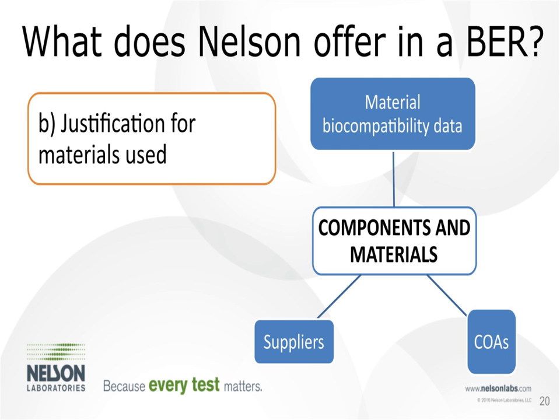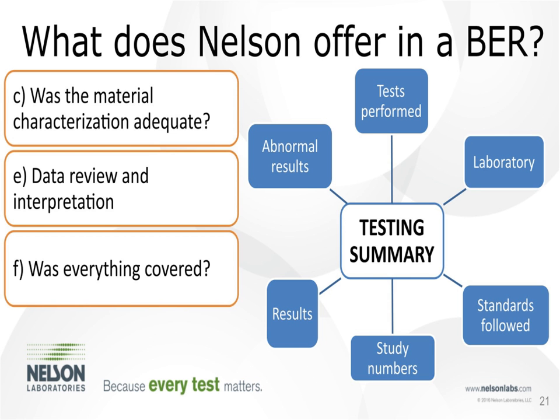The next section is Components and Materials, which can go into as much or as little detail as desired. It's important to lay out your awareness of your components and materials openly for the reviewer, showing transparency about what's in your device. We'll discuss your suppliers, any COAs or COCs (certificates of compliance), and present any material biocompatibility data your suppliers may have — which is great information if you're starting with a biocompatible material. This covers Section B of ISO Clause 7: justification for materials used.